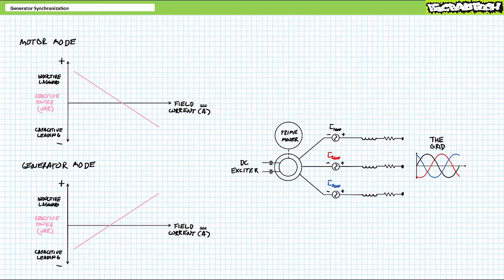This begs the question: could a generator do the same thing? Sure, why not? In this fashion, an electrically excited generator can export real power to the grid and power factor correct the grid. Often, one or more turbines in a large collection of turbines at a hydropower facility is reserved exclusively for this power factor correction role, and by dynamically adjusting field current, it will thus balance reactive power requirements for the grid.